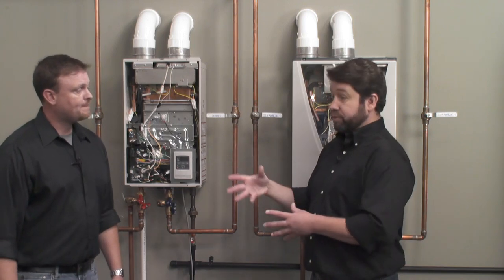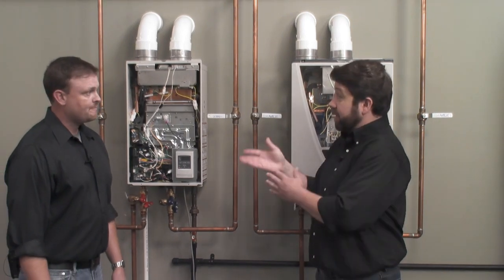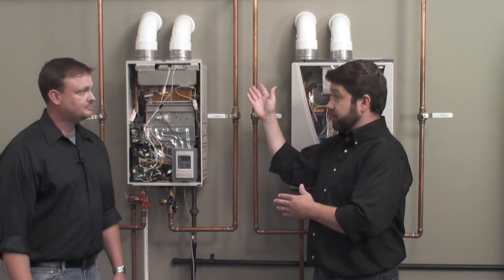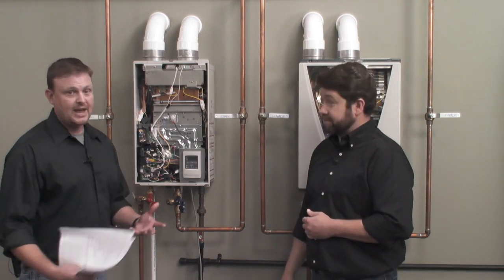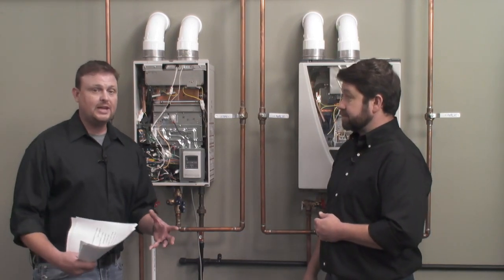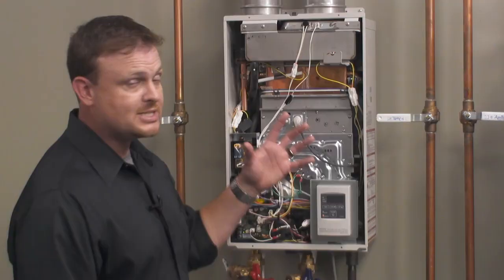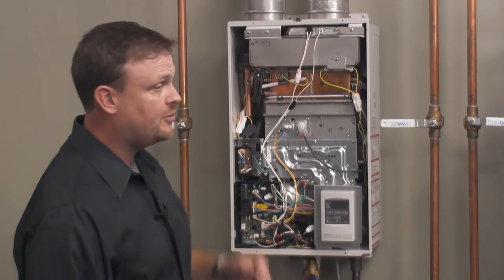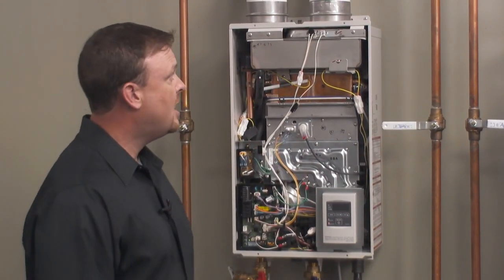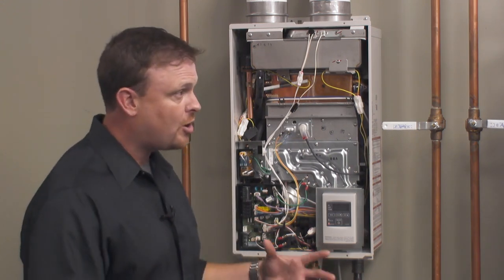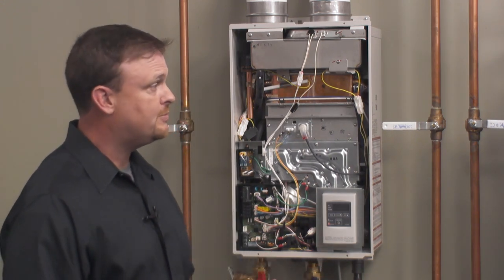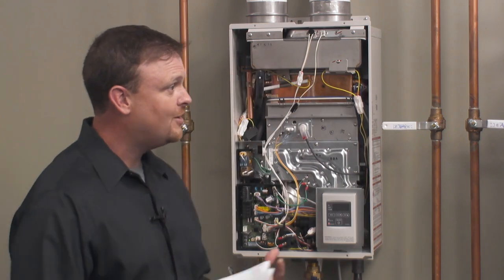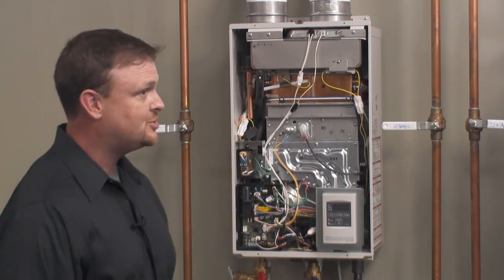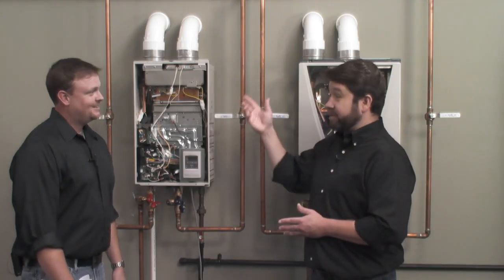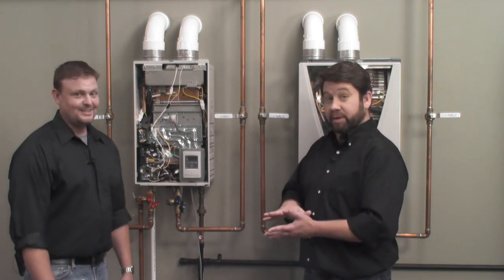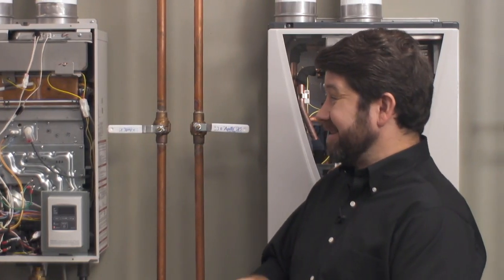So a lot of the heat energy from burning the gas is going into the water. We're not losing very much at all out of the flue. Okay, so that's why it actually condensates. That's why the vent temperatures aren't as high, and we're able to use PVC pipe. If you look up there, we've got PVC pipe on there. Since we're putting all of that heat into the water, it cools those flue temperatures off to where we're making rain and we have condensation. Absolutely. Because we're using PVC, we want to keep those flue temperatures underneath 140 degrees. The way we do that is really neat.